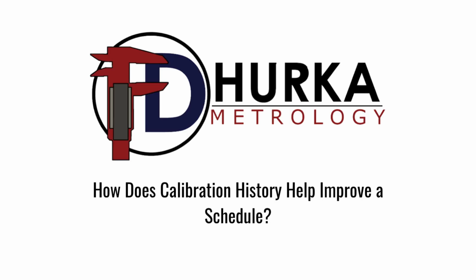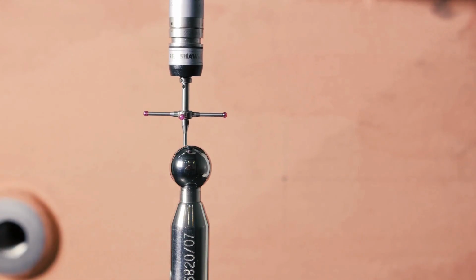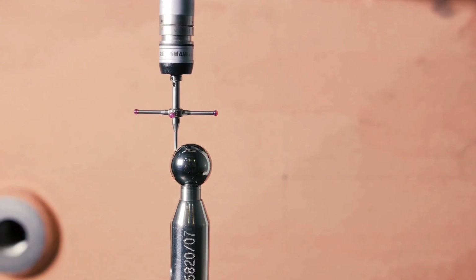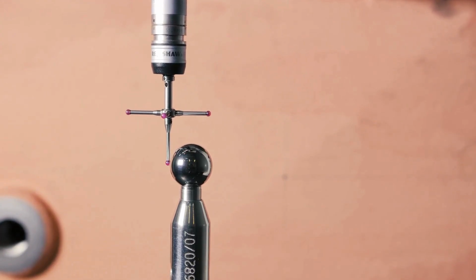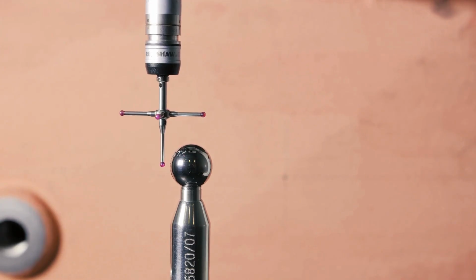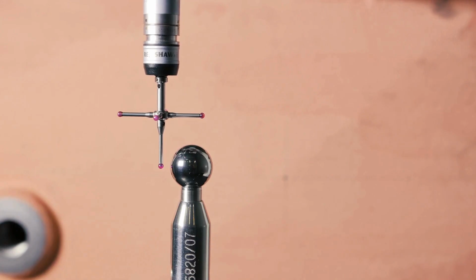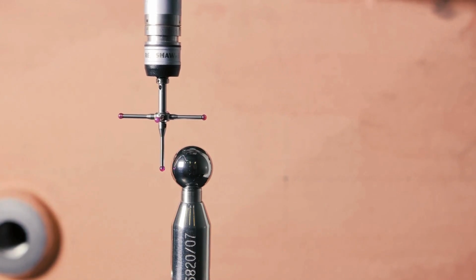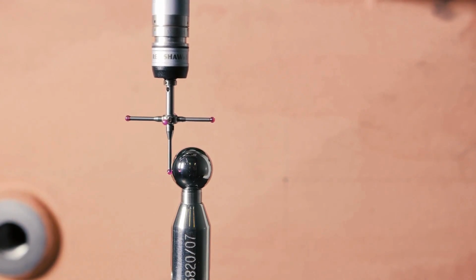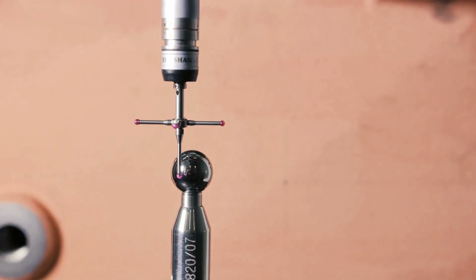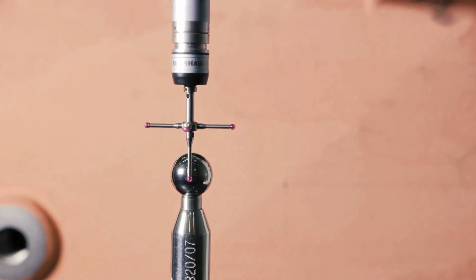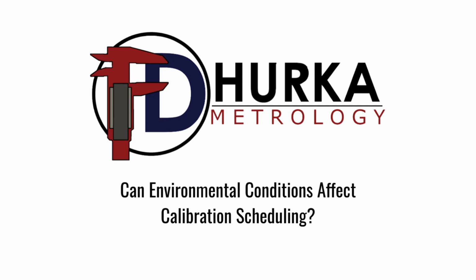How does calibration history help improve a schedule? Calibration history can show whether an instrument stays stable over time or tends to drift, which helps a facility decide whether intervals should stay the same, be shortened, or be extended. And this is where good record keeping moves from a paperwork task to a tool for making smarter, evidence-based scheduling decisions. Can environmental conditions affect calibration scheduling?